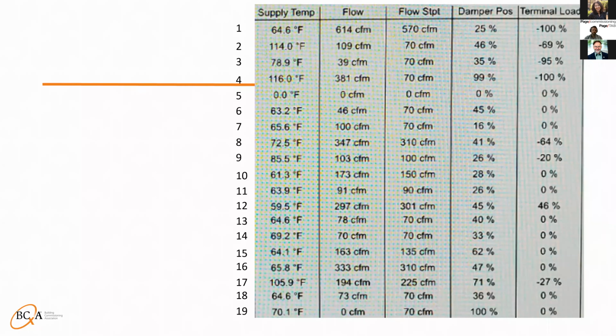So let's assume the first row is box 1. We can probably assume boxes 1 through 4 are still modulating to set point, but what's going on with box 5? This could be a communication issue. What's going on with box 7? 16% damper position and still above set point. If this box is not at the beginning of the run, there may be a calibration issue, or maybe the box is oversized. All other terminal unit damper positions are considerably more open.